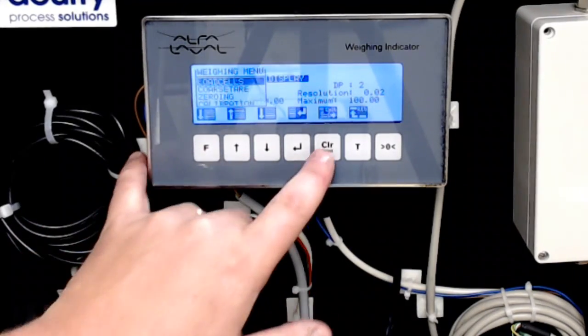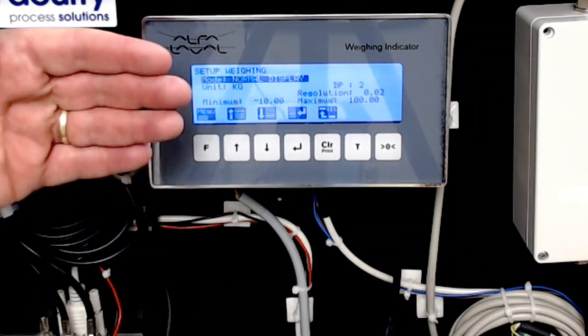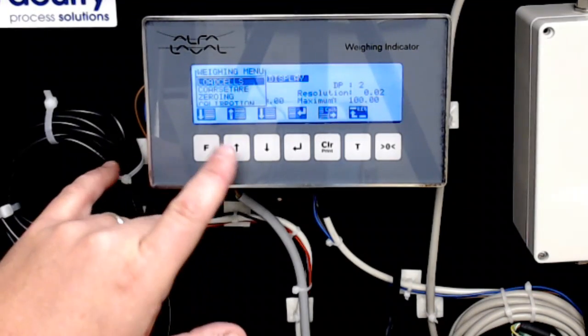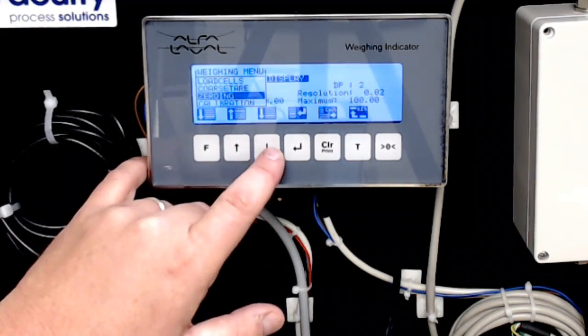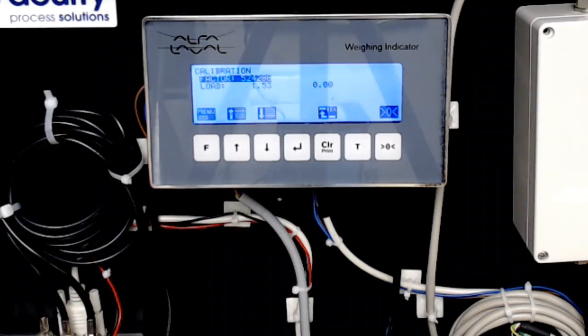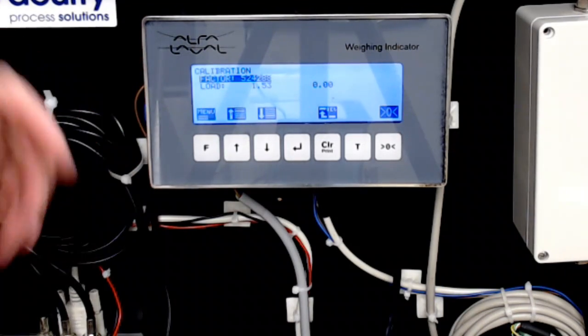Now, let me back up here and I'll show you what I'm talking about. If we're in that weighing mode and we hit menu, we just did the coarse tare. Let's move down and do the calibration. If we look here, this is the factor I was talking about. The system applies that to the signal being generated by the load cell to convert that signal into a weighing number that we understand. So whether it's pounds or kilograms, the factor is the same, but it's applied to teach or tell this module what it means.